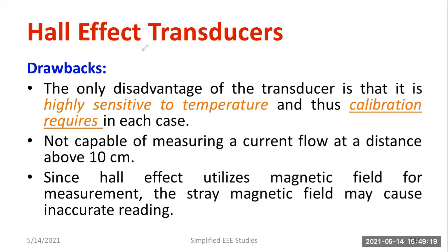The major drawbacks of the Hall effect transducer are: some Hall effect elements are sensitive to temperature; calibration is a somewhat tedious procedure; extending the range is difficult; it is not capable of measuring distances above 10 centimeters; and since it utilizes a magnetic field for measurement, stray magnetic fields may cause inaccurate readings. Any variation in the magnetic field due to stray fields will vary the Hall voltage, leading to errors, and accuracy is poor compared to other measurement types.